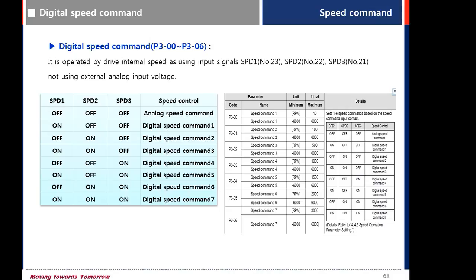For example, if you want to use digital speed command 3, firstly set the speed value in parameter P302, and then set digital input signal speed 1 and 2 on, and speed 3 off.